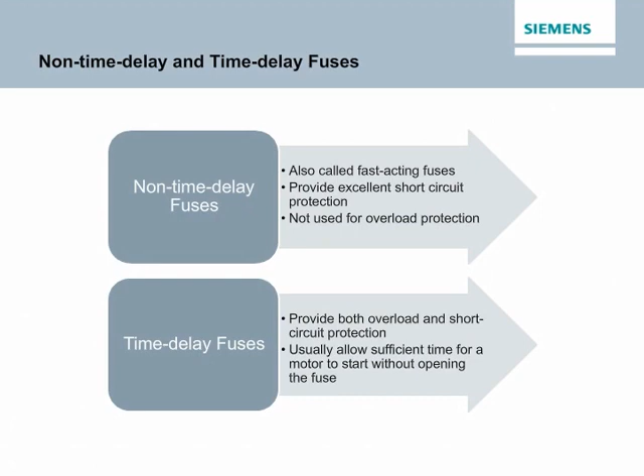Time delay fuses provide both overload and short circuit protection. Time delay fuses usually allow 5 times the rated current for up to 10 seconds. This is normally sufficient time to allow a motor to start without nuisance opening of the fuse. However, a longer lasting overload will cause the fuse to open.